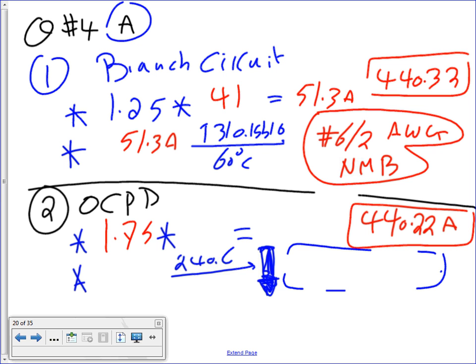That's your conductors. Now I want to bring to your attention tomorrow, guys, one little thing. This number right here will be called minimum circuit ampacity. You guys hear me? So, Dirk, my friend, when the manufacturer has on the nameplate minimum circuit ampacity, that's also on the test, by the way, on the theory test. Minimum circuit ampacity, do you need to multiply by 1.15 or 1.25? No, it's already done for you. You see where after you multiply by 1.25, that number is called minimum circuit ampacity. So you don't have to multiply by anything.